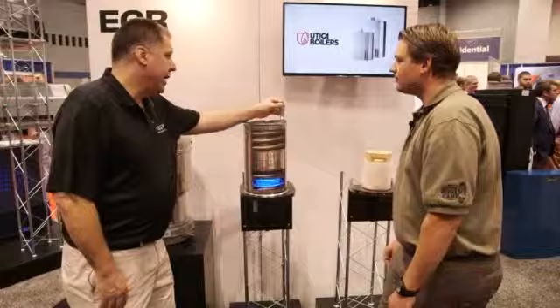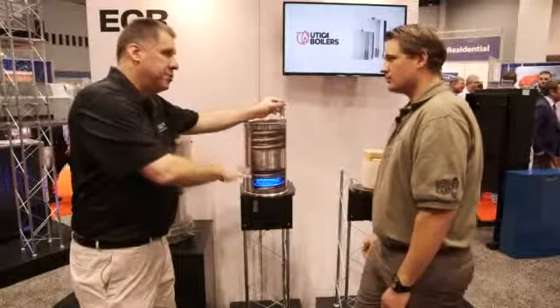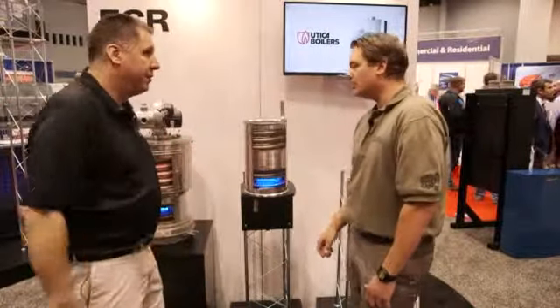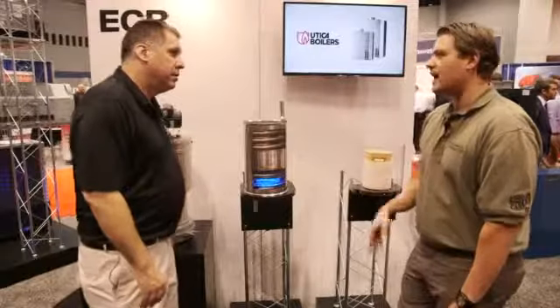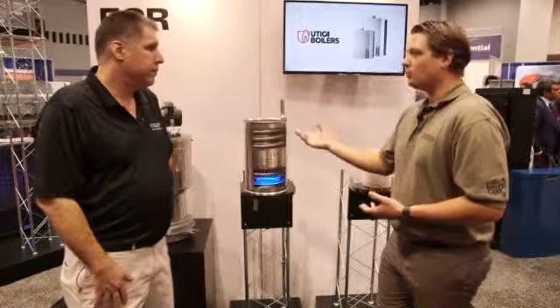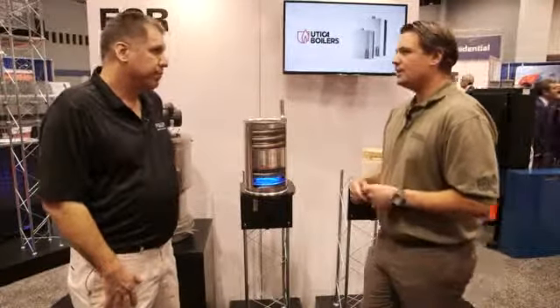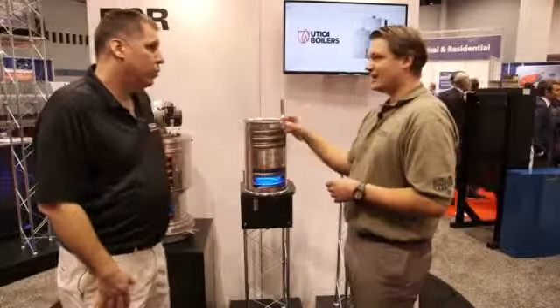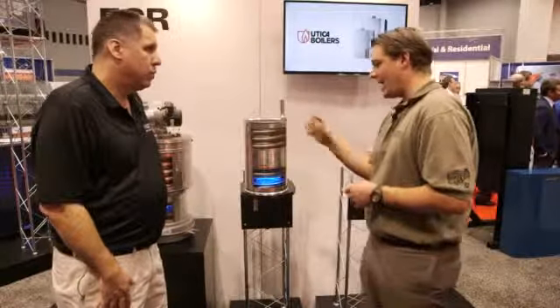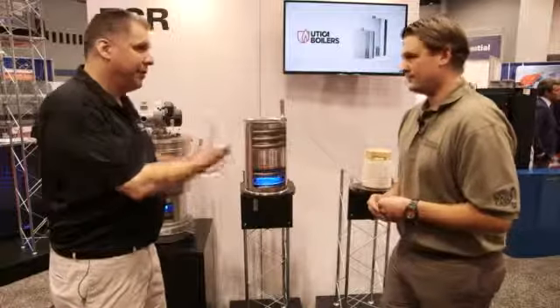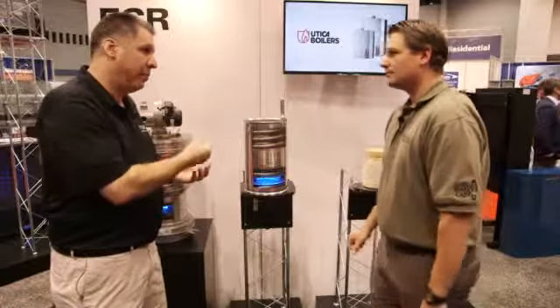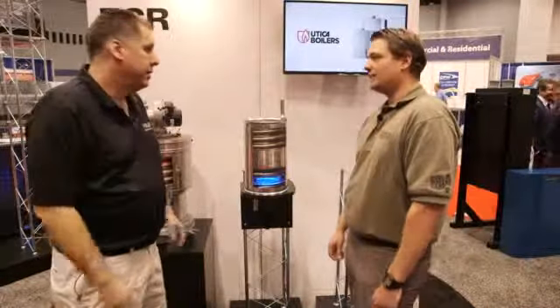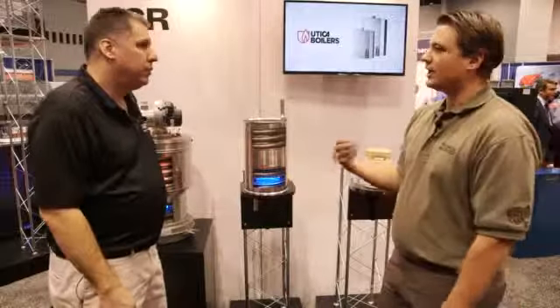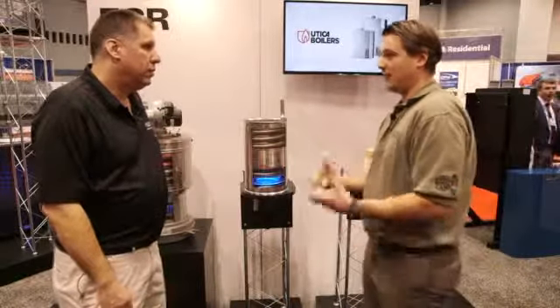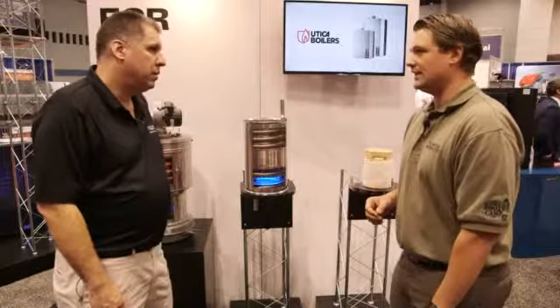So with the wide passageways, you have a low pressure drop. You don't need a high head pump. Yep, you don't need a high head pump to run the boiler, and that does help. One of the unique things is that wide passageway for the water side. So if debris were to come through there, it doesn't get stuck inside the tubes, it would pass right through and out the other side. It flushes out and stays clean on both the inside, the boiler side, and on the combustion side. Yes. Even on the internal side, if you get coating in there, the expansion and contraction of that pipe can break that free to keep the heat exchanger clean.